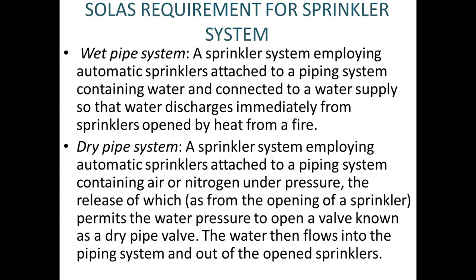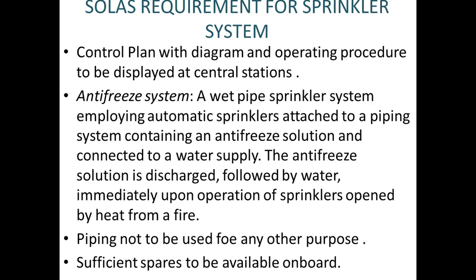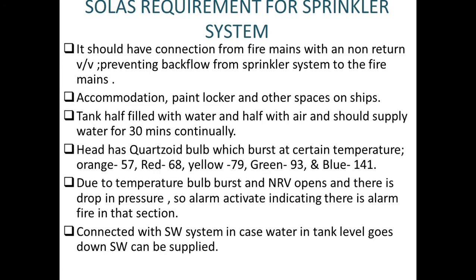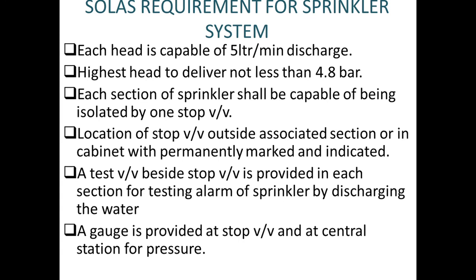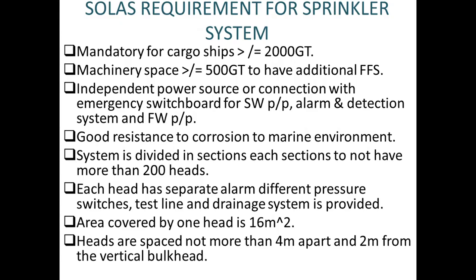I hope all these, the wet pipe system, dry pipe system, antifreeze, the controls, how much area it is covering, for how much time, the temperature for the quartzoid bulb, the seawater system as well as the freshwater system, are clear. The test valve is there, the drainage system is there, how many sprinkler heads are to be available, at the highest available point what the pressure has to be, and the head capacity, meaning how many liters it can discharge. For which ships it is required, how much area one head covers, all these points we have covered very minutely and finely.